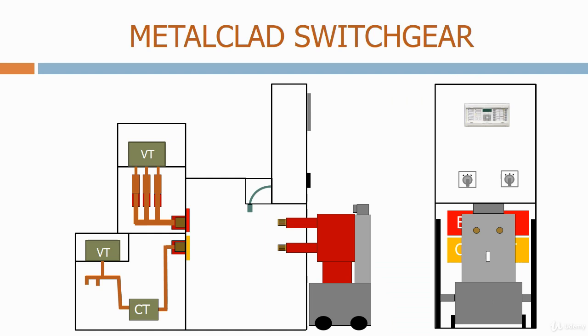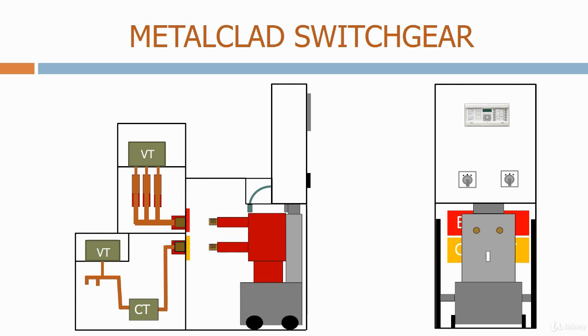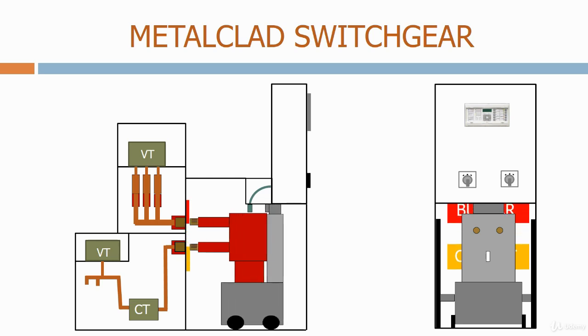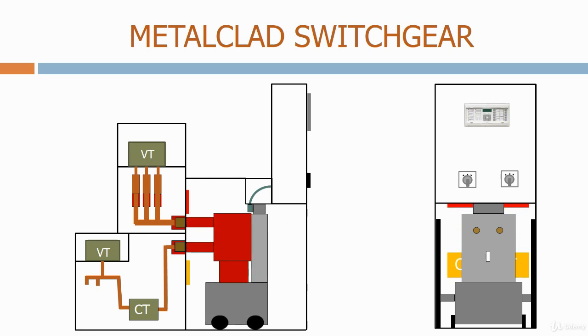Let's now push the truck into the circuit breaker chamber. Normally, the truck can only be pushed into the enclosure so far by hand. From this point forward, the truck needs to be wound in using a winding handle. This ensures that when the circuit breaker contacts come into contact with the busbar and circuit terminals, it's done in a controlled way. As we can see, the shutters open, allowing access to the contacts behind. When the truck has been fully inserted into the circuit breaker chamber, the secondary terminals at the top of the truck make full contact with the secondary terminals for the panel enclosure. The panel now has full control of all the trip and close functions of the circuit breaker.